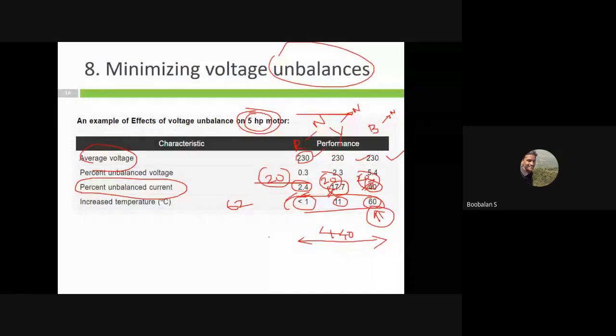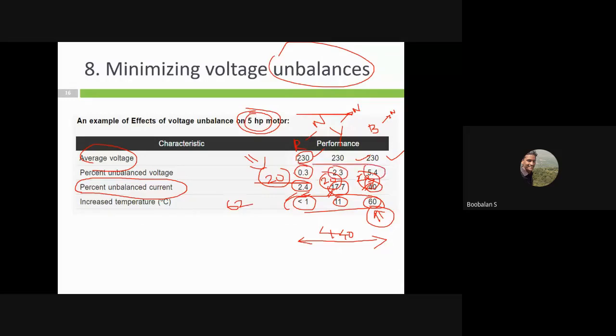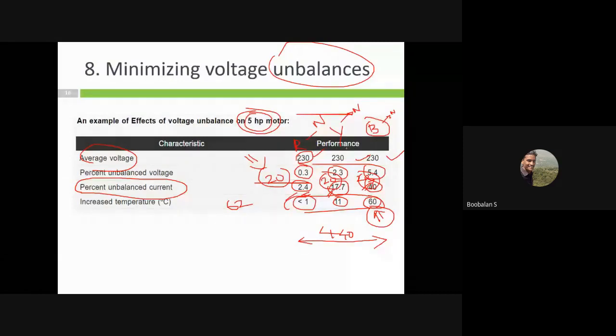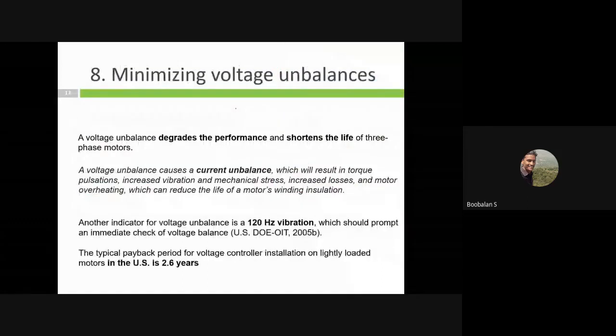So how can we detect this - we need to go with IoT based sensors. We fix current sensors, voltage sensors, and every data comes from this motor every second, and we have a program. Based on the program logic, it will indicate if some motor is consuming much energy in a particular phase. We get a pop-up trigger message, then we immediately call the section manager and operator to stop that machine and do a debugging technique. By doing this checking and minimization, we could achieve a payback in about 2.5 years using this technique.